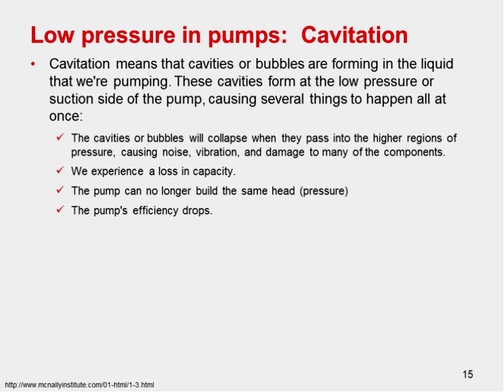Now, I wanted to mention this because this is really neat. One of the concepts is how we use thermal fluids concepts in civil engineering. Whenever we have low pressure or high pressure, it affects our system. In pipes and in areas near pumps, we can have a problem called cavitation. Cavitation means that bubbles form in the liquid that we're pumping, and these cavities or bubbles form at low pressures on the suction side of the pump.